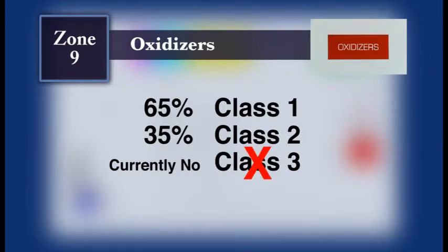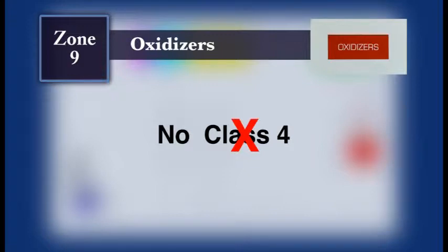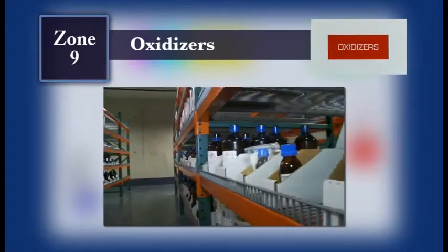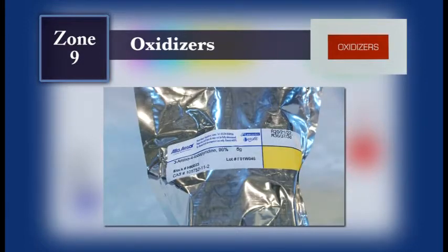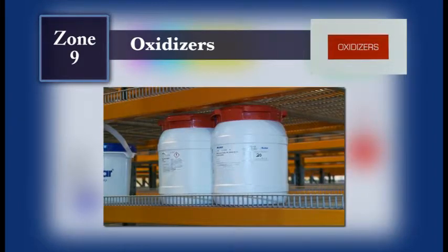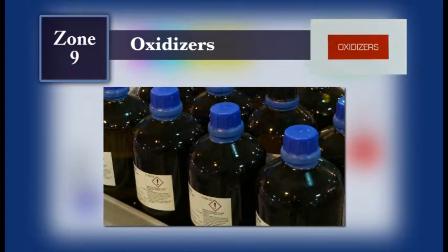However, should Class 3 oxidizers be placed into inventory, dedicated storage cabinets specially constructed to house this material will be provided. Dedicated containers for Class 3 oxidizers typically have the capacity to hold 4 55-gallon drums. These containers are designed to be connected directly to the sprinkler system so that the high sprinkler flow densities required for Class 3 oxidizers is limited to the storage containers rather than applied to the entire space. No Class 4 oxidizers will be held in inventory at this location. Product is primarily in the solid state and is stored in cardboard boxes, bags, and other similar smaller containers, with some products stored in 5 to 10 gallon pails. Hydrogen peroxide may be stored in plastic drums, and nitric acid is stored in glass containers.